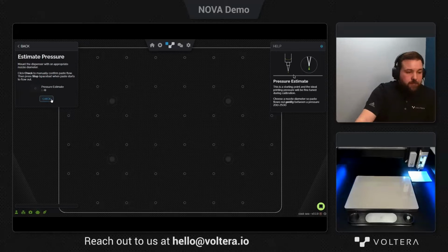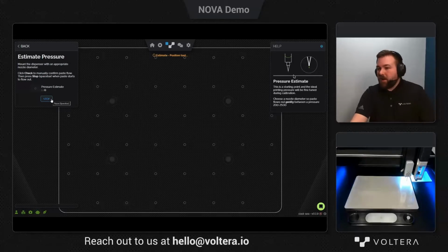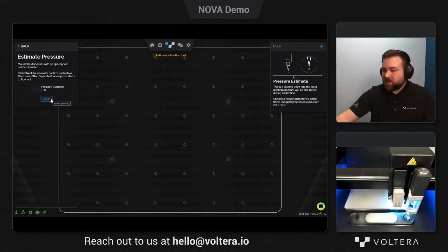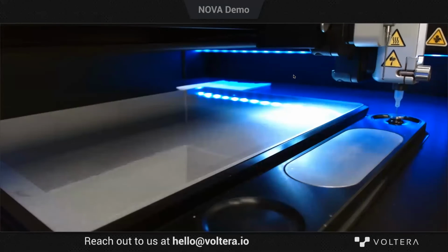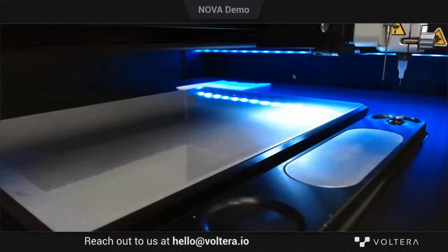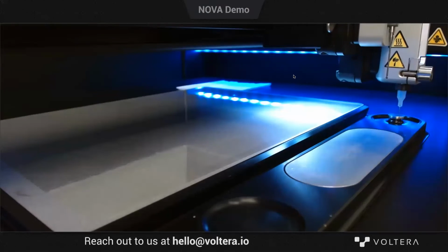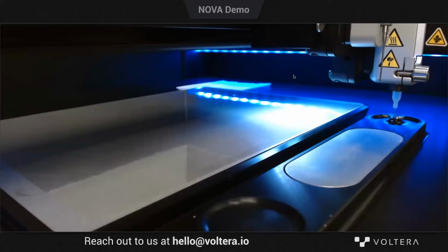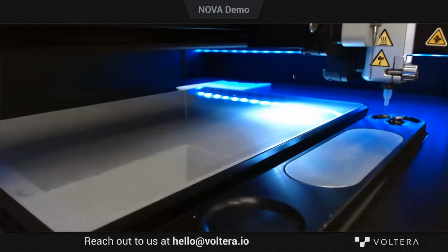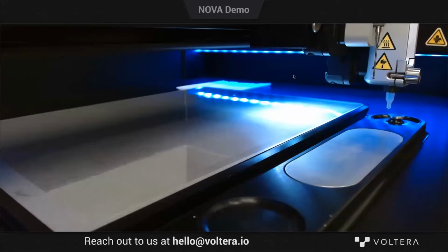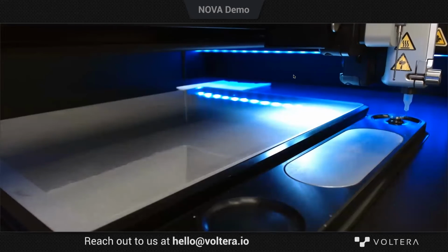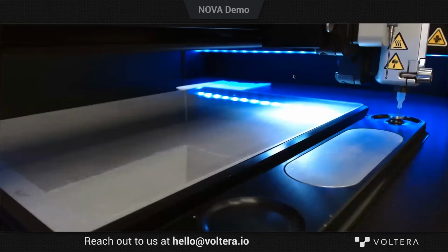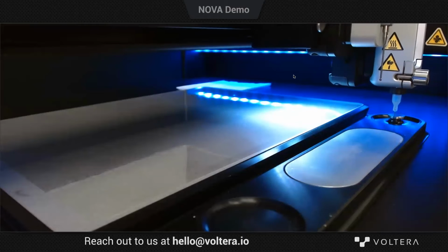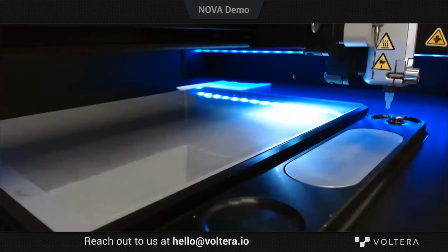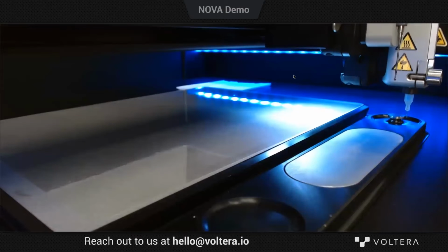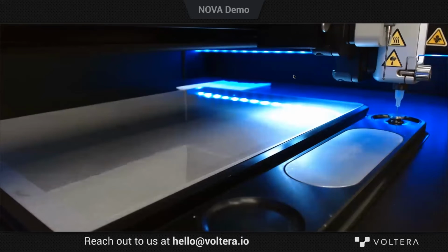Perfect. So I'm just going to click check. And we're going to see our dispenser move over to the XYZ positioner switch here in order to measure itself. So we can see it getting its Z height there. And then it's going to move in a second to get its X positioning. So it's going to tap on either side of the switch. And then we calculate the center based on that. And it's going to do the same thing in the Y direction there. And once it's done, we'll know exactly where the tip of that nozzle is, and we'll be able to print with it.